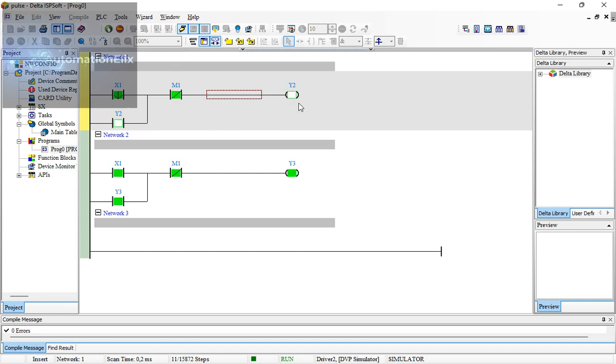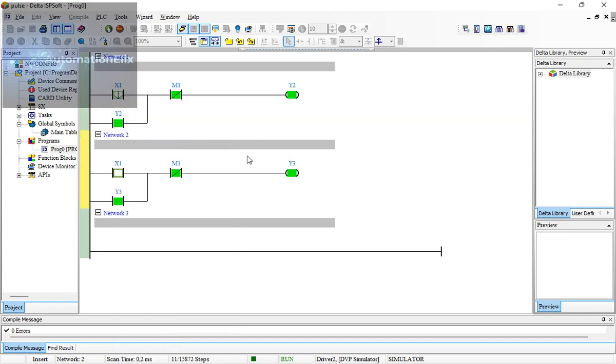So when you've got a motor that is running, the moment you switch off the motor, you want to start another motor, you use a falling edge. So let's say another motor is switching off now, that's when this one goes on. So it only responds when something is switching off. When something is switching off, it switches on something, it gives you a falling edge.